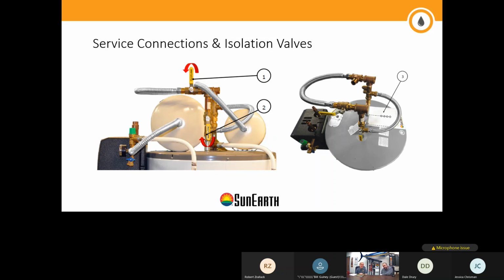Very excessive. If a bank of collectors has 6 to 8 collectors, or you might call them arrays in PV, yes, those can be isolatable. And obviously, if you have shutoffs on something that can produce heat, you have a relief valve in that circuit that cannot be isolated. Same thing with the example that you see here. It's a bypass that we install on our residential hot water stations.